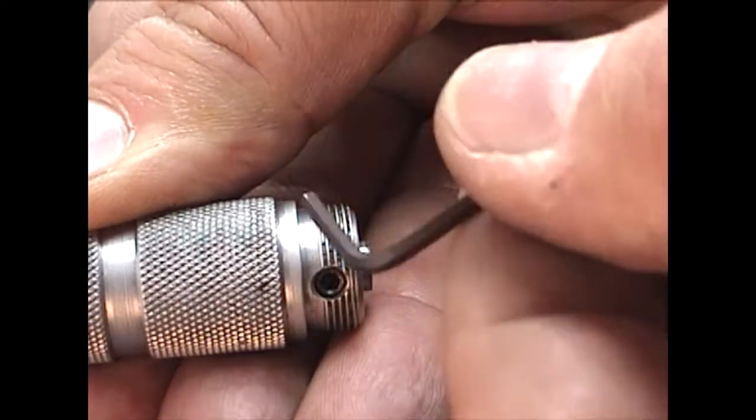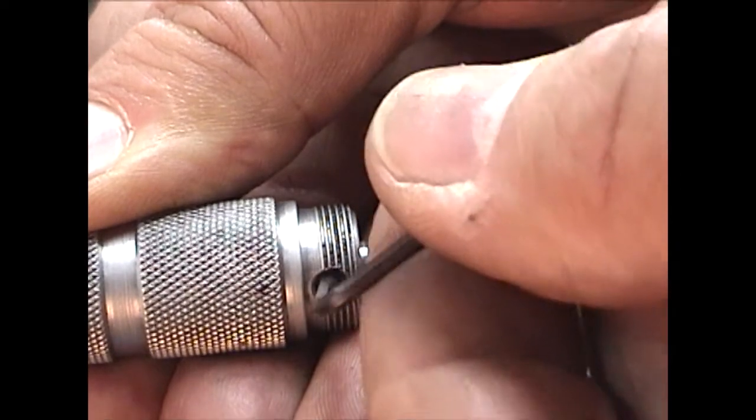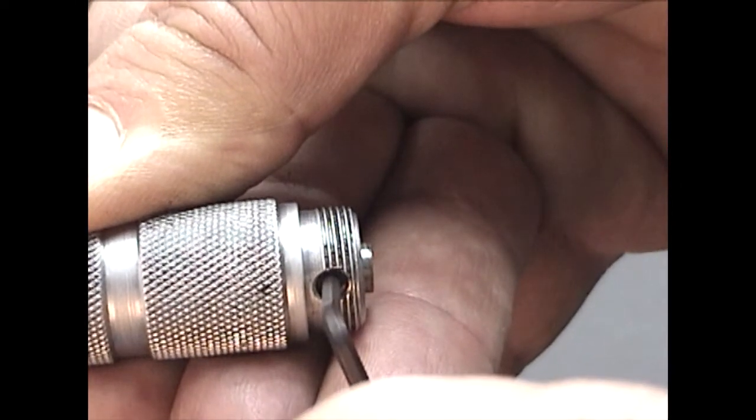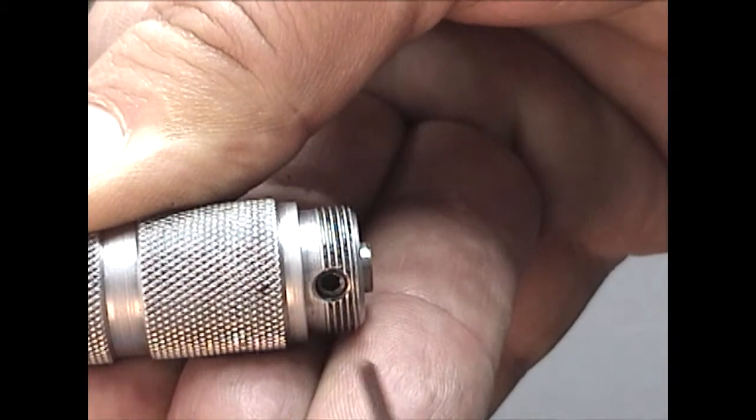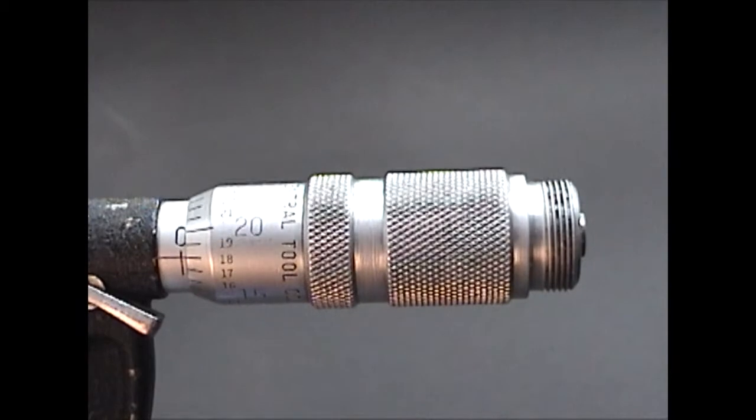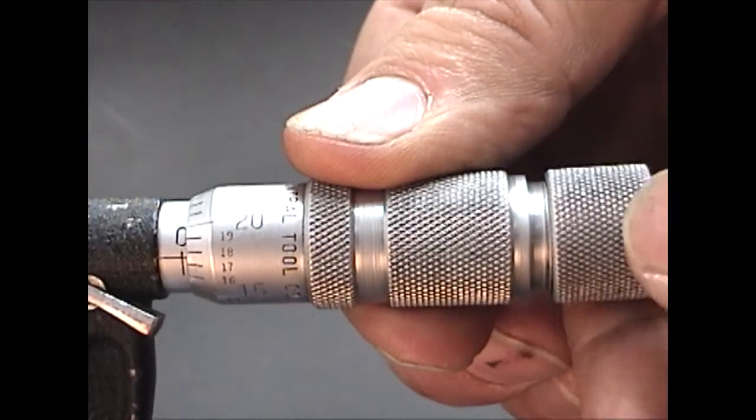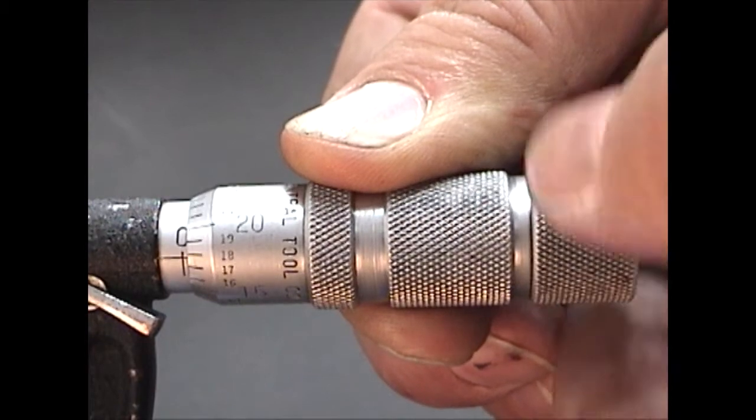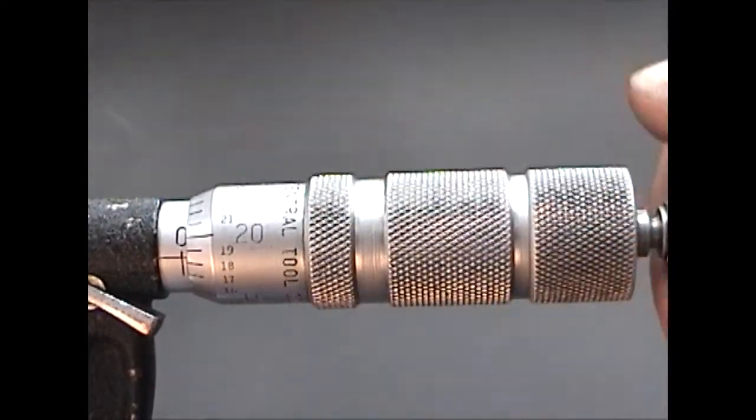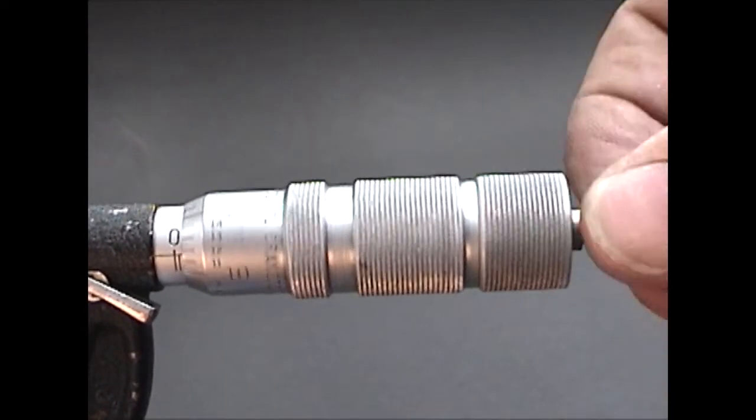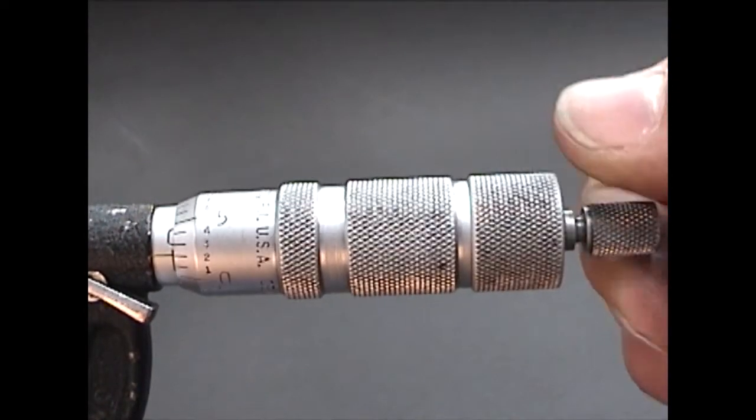Fully tighten the set screw so the thimble won't move. Install the ratchet cap. Check the calibration once more with the thumb ratchet.